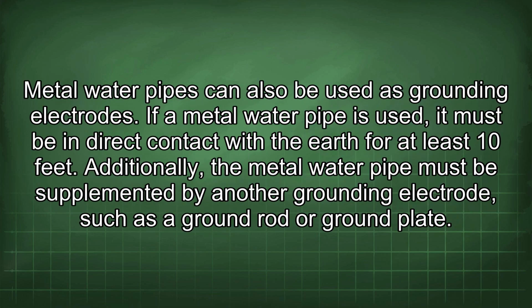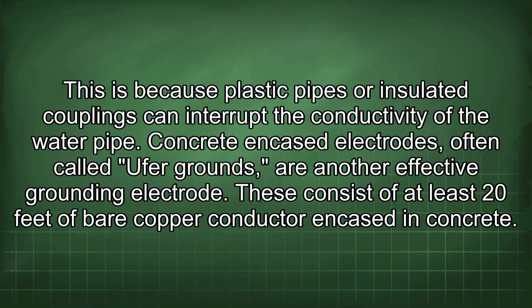Metal water pipes can also be used as grounding electrodes. If a metal water pipe is used, it must be in direct contact with the earth for at least 10 feet. Additionally, a metal water pipe must be supplemented by another grounding electrode, such as a ground rod or ground plate. This is because plastic pipes or insulated couplings can interrupt the conductivity of the water pipe.